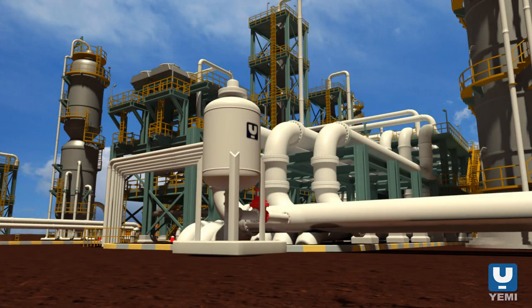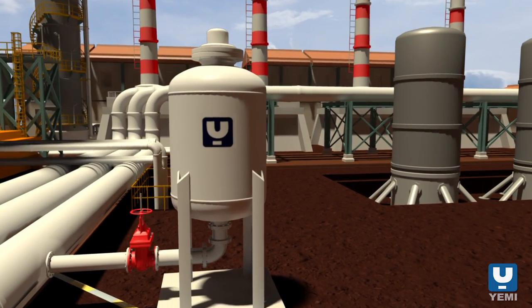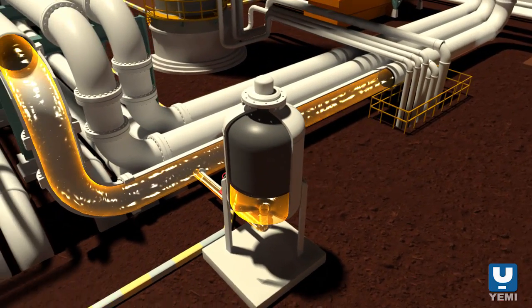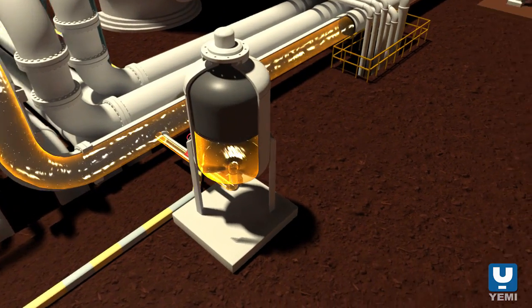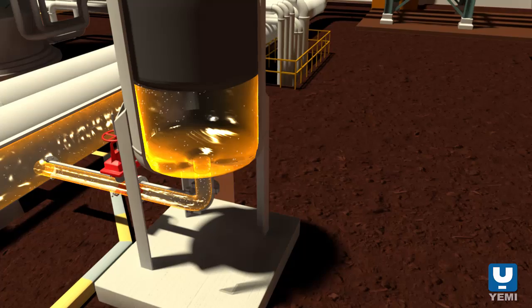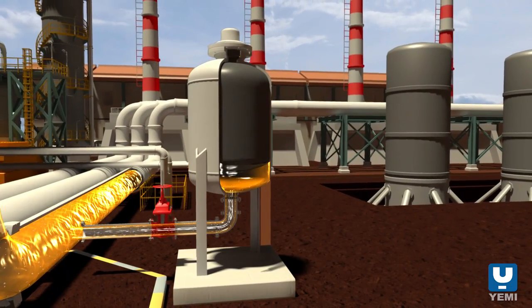A more innovative and effective solution is a self-contained bladder surge tank. The bladder surge tank uses less space and constantly reacts dynamically to transient pressures with zero loss of containment. A bladder in the tank is charged with gas during installation and is monitored to determine when additional gas is needed. The bladder is the only moving part, absorbing pressure transients and allowing a nearly maintenance-free design.